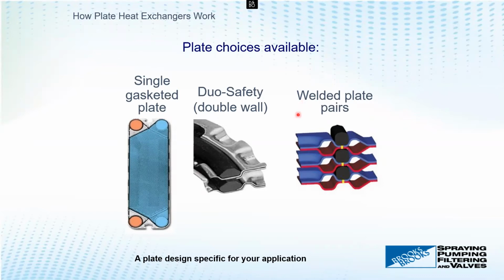And then we talked last time about welded plate pairs. What these are is every plate comes in a welded plate pair. So here we have welds around the entire outside surface of the plates, and those plate pairs are now put together by gaskets. This is for if you have something that you absolutely cannot have get to atmosphere, you can't have any leaks to the ground, can't take even a remote risk. You're going to have that entirely contained in here by welded plates. So should you have hydrocarbons you can't let out, ammonias you can't let out, anything like that, it's fully contained within a welded plate pair.